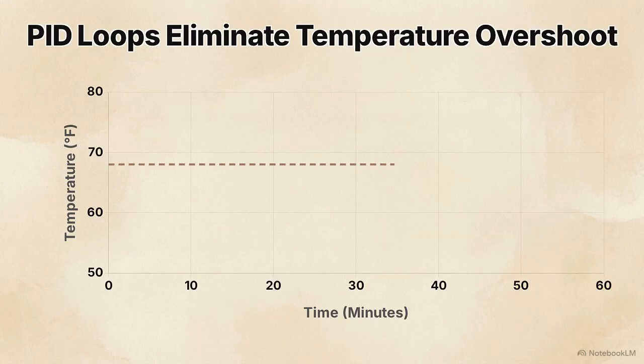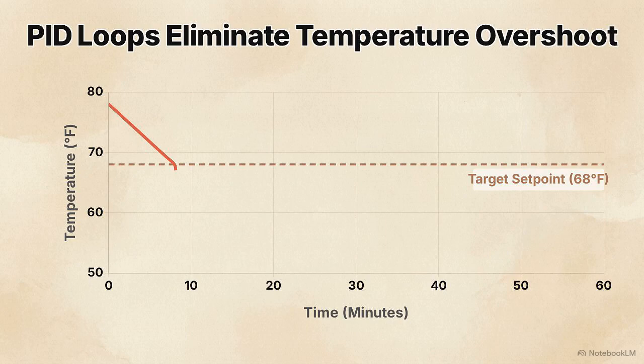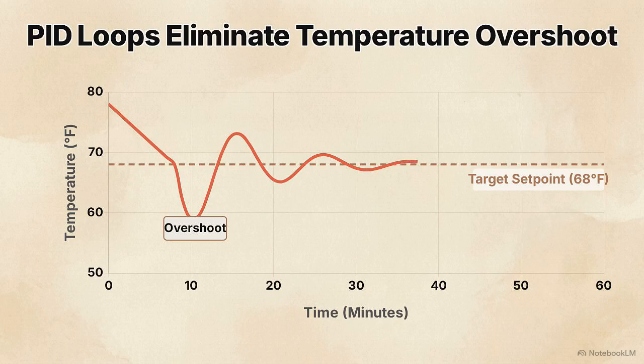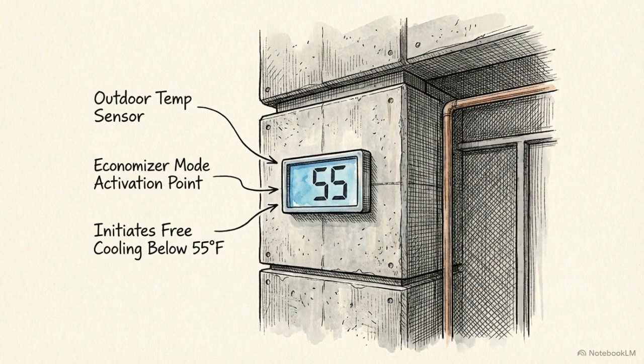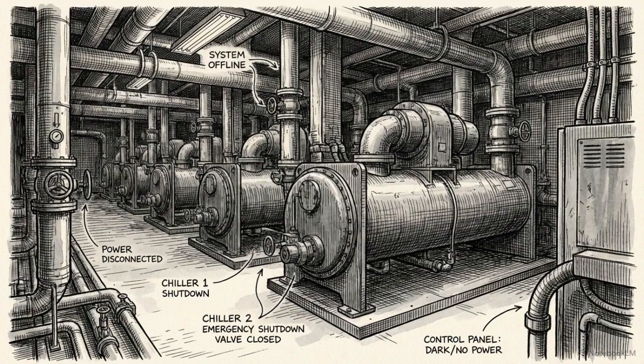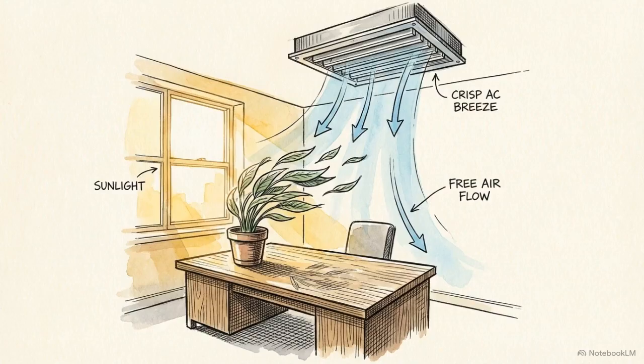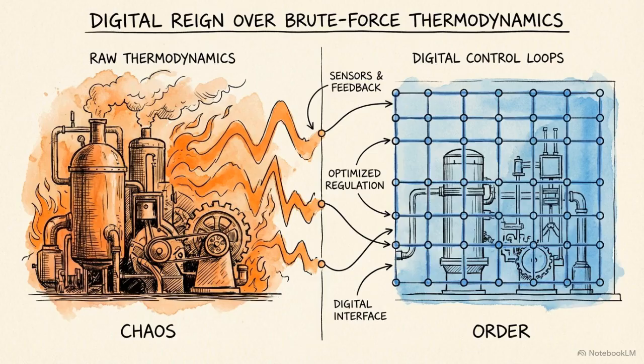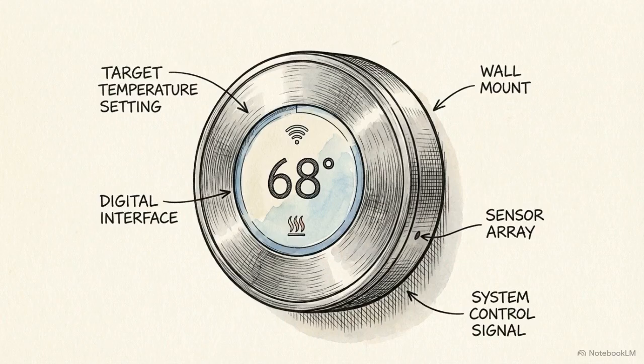The system regulates the water valves using PID loops. A PID loop is a continuous mathematical calculation that measures the difference between your desired temperature set point and the actual room temperature, allowing the system to gently adjust the cooling output without overshooting the target. And when the outside temperature drops to a crisp 55 degrees, the BMS activates economizer mode. It completely shuts down the energy-heavy mechanical chillers, opens the exterior vents, and uses the naturally cool outdoor weather to provide free air conditioning. These digital control loops and sensor networks, reining in the brute force thermodynamics at the chiller plant, turning a raw industrial process into a precise, on-demand utility.